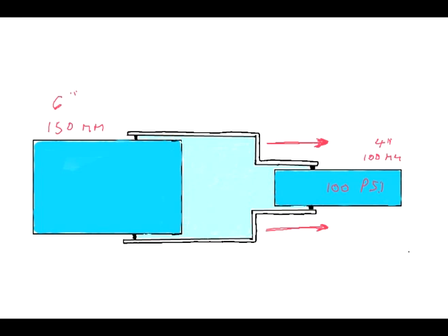Now, if you think about the thrusts that are pushing from the 6-inch against the 4-inch, they're not quite balanced. I hope you can see from this sketch that this tendency will cause the coupling to try and push in the direction of the red arrows, and actually could potentially push right off the 6-inch pipe, and therefore you would have a leak. Now, what's stopping this from happening under normal conditions?